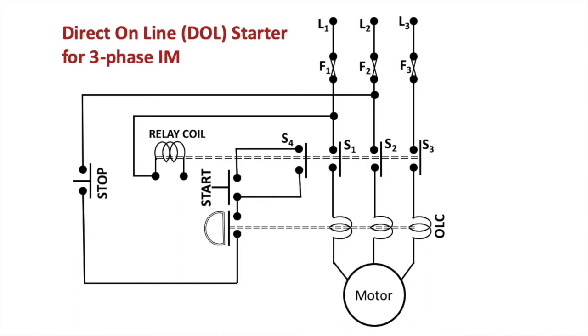This start button, overload relay, stop button and the relay coil are connected in series to each other. The overload relay's basic function is the thermal protection of the motor. If the motor current exceeds a certain limit and the temperature rises beyond a given level, the motor is said to be overloaded, and thermal protection is provided to the motor through the OLC, the overload coil. The relay coil functions as a voltage coil: if the motor is running and the supply goes off, this relay coil will be de-energized and it will open the switches S1, S2, S3. So the motor will be disconnected from the supply. Again, if the supply resumes, the motor won't start on its own unless you press the start button.